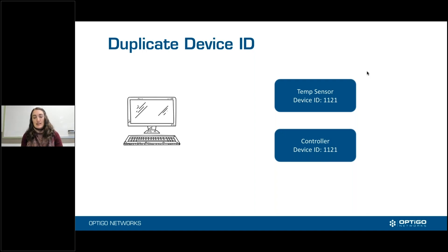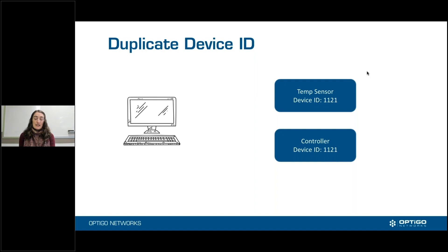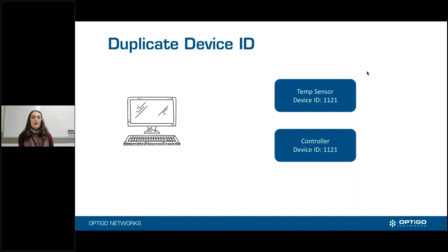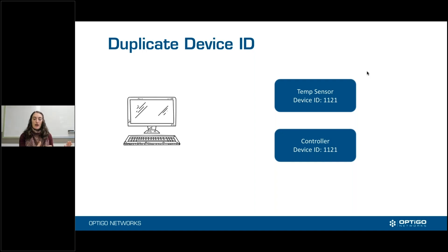So very likely, in this example, the controller is supposed to be device 1121, and the temperature sensor is supposed to have a totally different device ID. Device ID is synonymous with BACnet ID — it's that device identifier. It may be that someone copied and pasted all of the configurations from one subnet to another, or this is a preset. 1121 probably isn't a preset, but that is often a way that this happens — a device comes with a preset and someone forgot to change it.